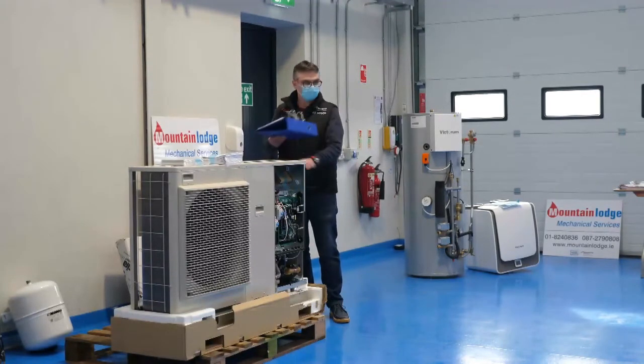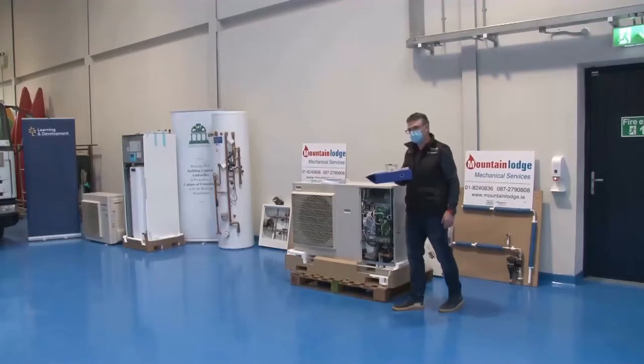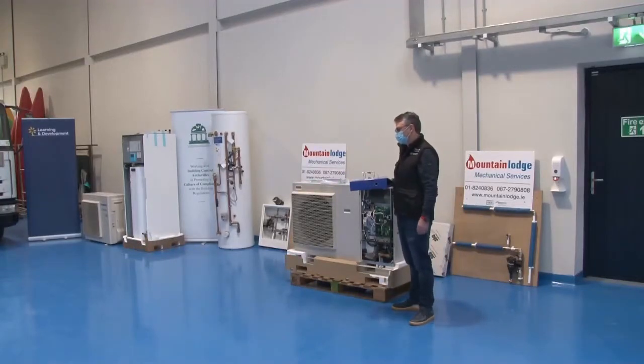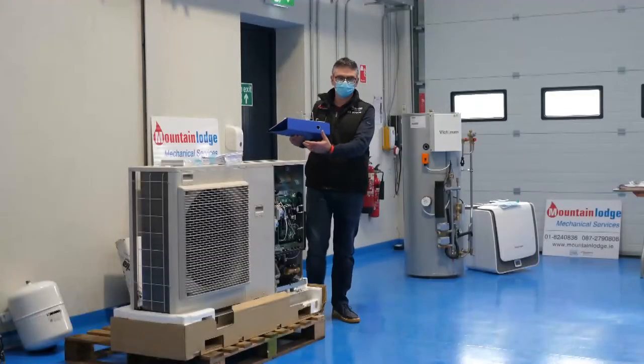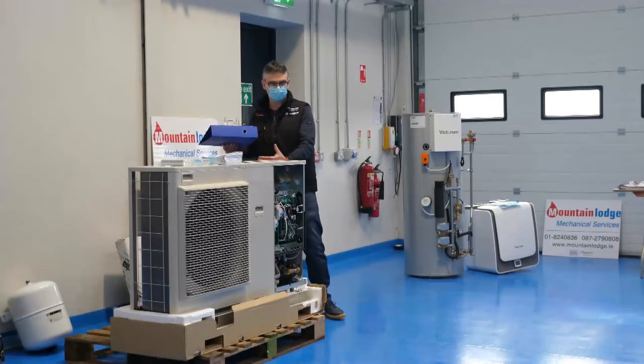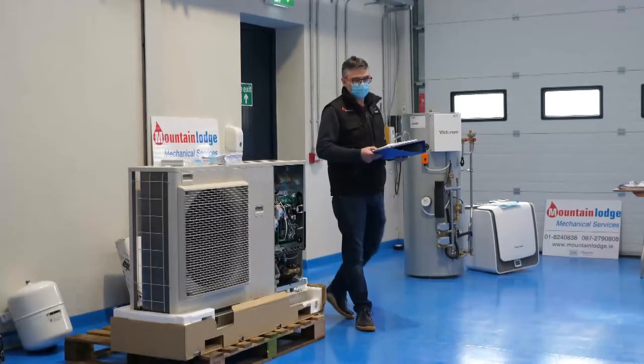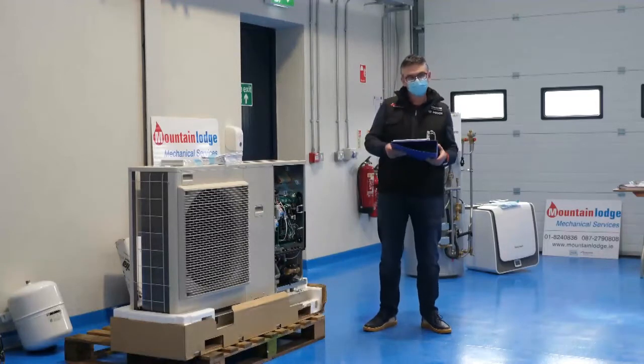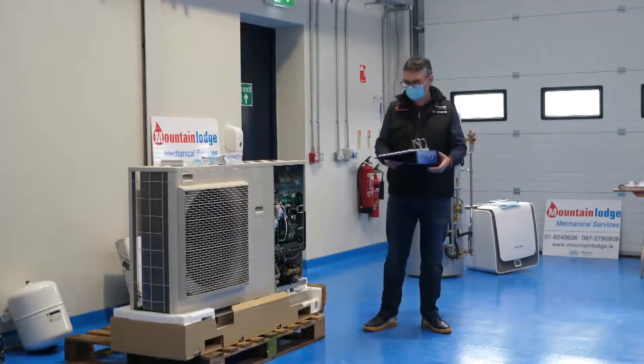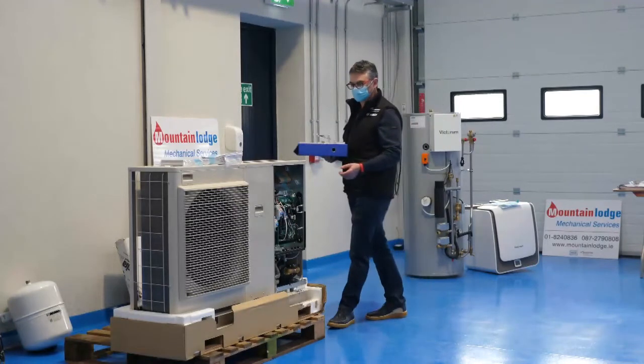You mentioned the cages earlier on. That's when the cages come into place. There have been cases where somebody comes out and turns off the isolator. So a lot of local authority housing still has the cage, and the isolator will be inside the cage as well, so that it can't be messed with. And then of course the drip. That's really what you're going to see.